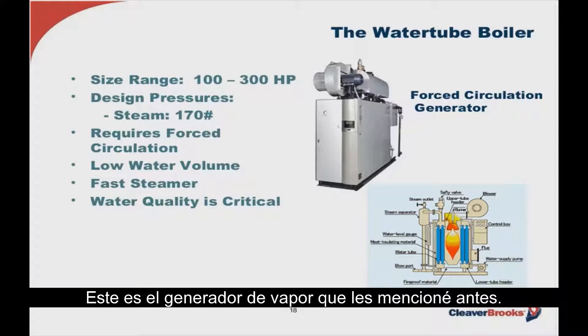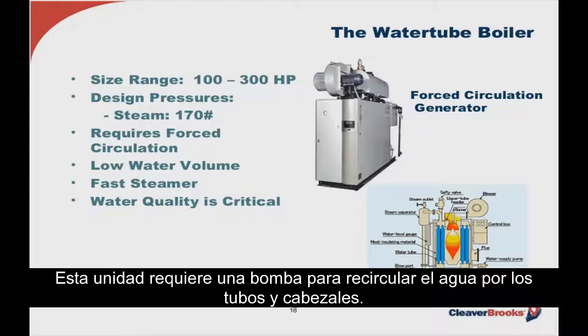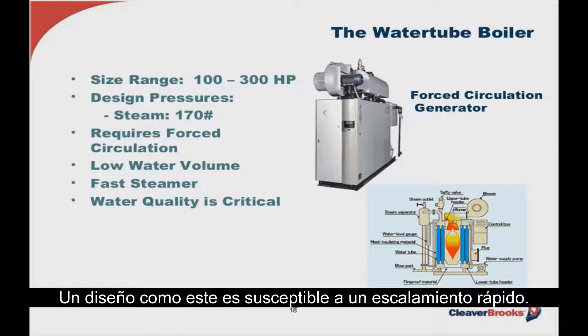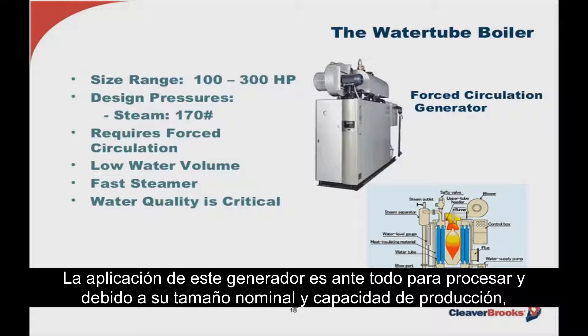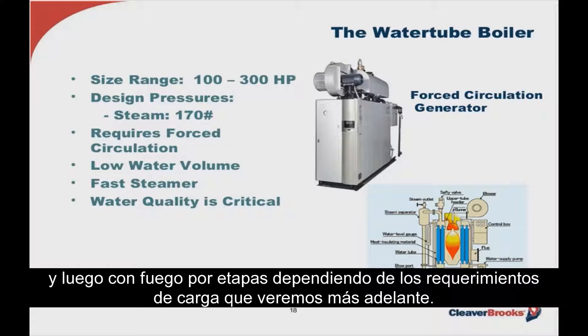Here is the steam generator — a vertical top-fired water tube boiler, but not a natural circulator. It requires a pump to circulate the water through the tubes and headers, and because of its very small water content, it can produce steam very quickly. However, it's also very sensitive to water quality as a design like this is susceptible to rapid scaling. Applications are primarily process, and because of its nominal size and output capacities, you often find multiple units sequenced through an integrated central control system and stage-fired based on process load requirements.